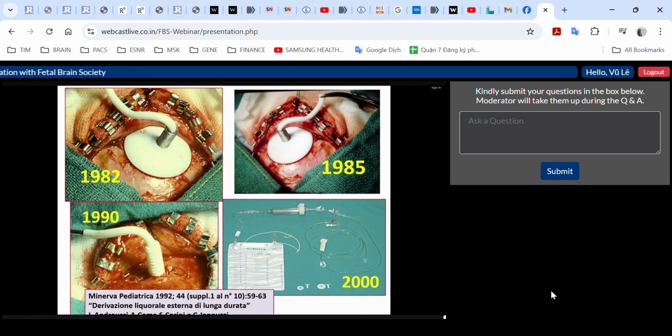The device has been specifically developed for pediatric patients younger than 30 days to prevent any CSF leakage. The 2.6 millimeter diameter of the hollow bolt has been designed to precisely fit a ventricular catheter with an outer diameter of 3 millimeters or more. The elastic property of the catheter allows complete adherence to the internal wall of the screw, reducing the risk of dislodgement.